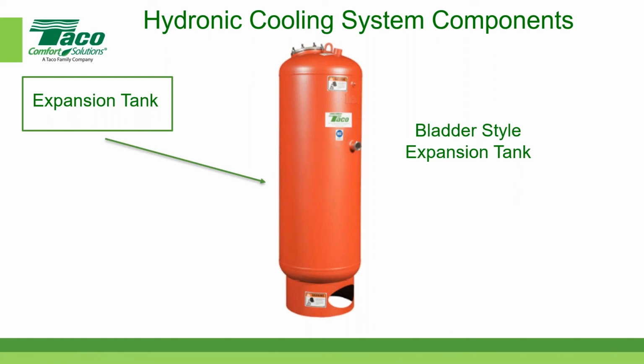So when you put the expansion tank, you connect it to the suction side of the pump, it maintains a constant pressure on the suction side of the pump, which is really important in order to maintain the proper operation of a pumping system. Isn't that cool? Yep. Okay.